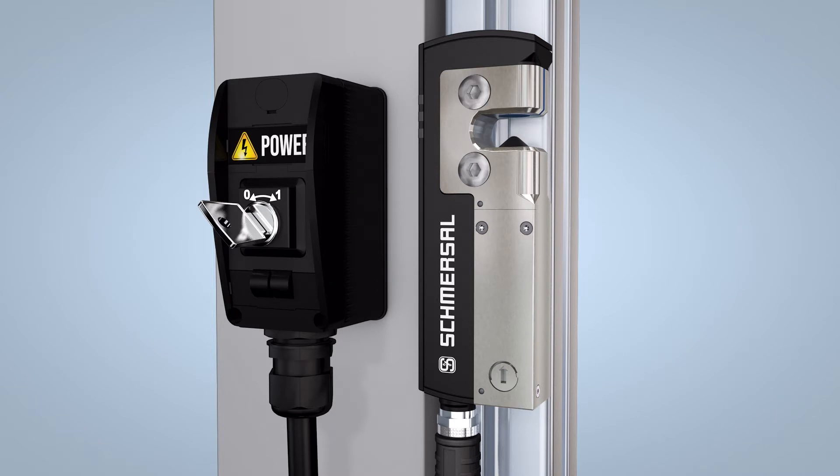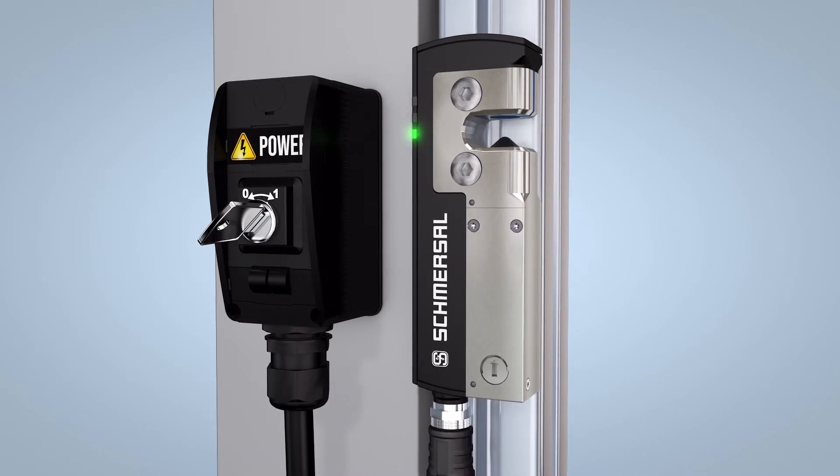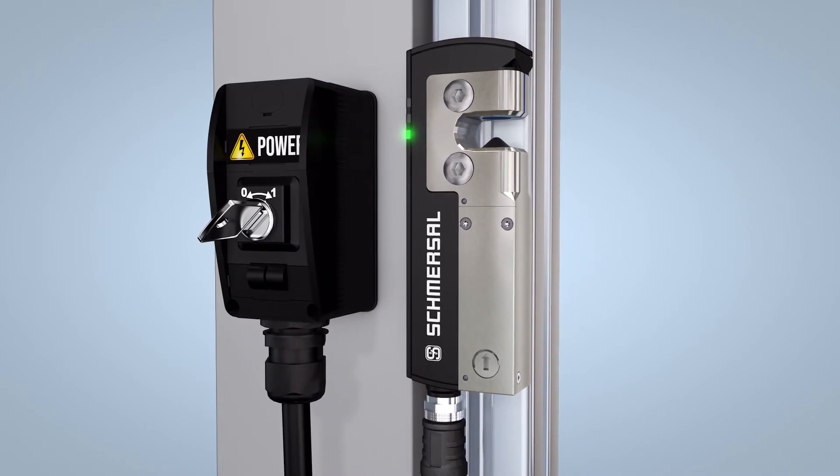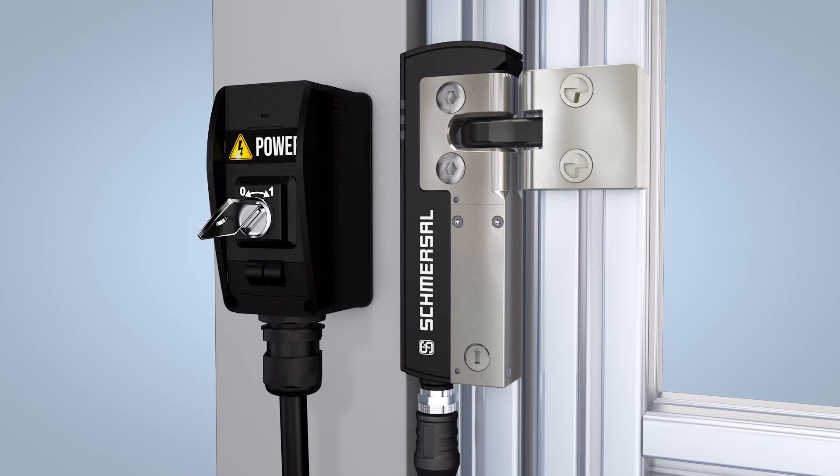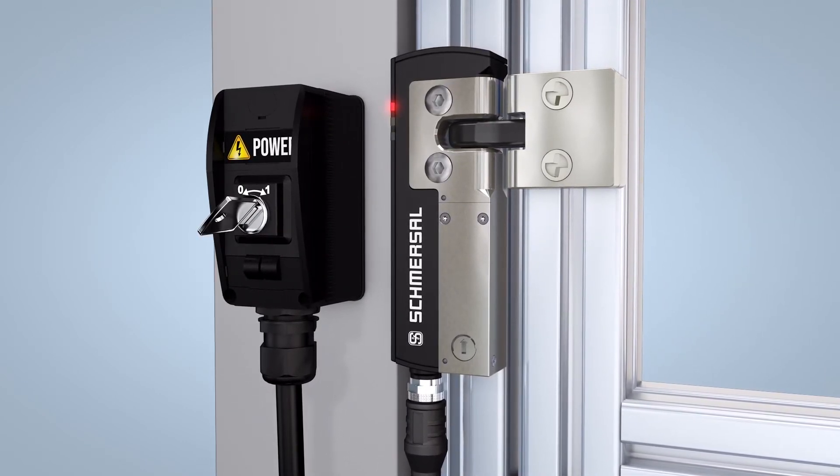Individually coded solenoid interlocks and actuators can be taught in very easily. Start by switching the solenoid interlock off. Then reapply the power and move the actuator to the detection area. The teach-in is signaled on the solenoid interlock by the red LED illuminating and the yellow LED flashing.